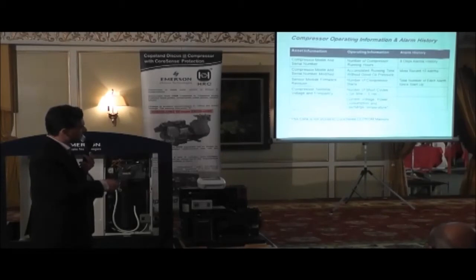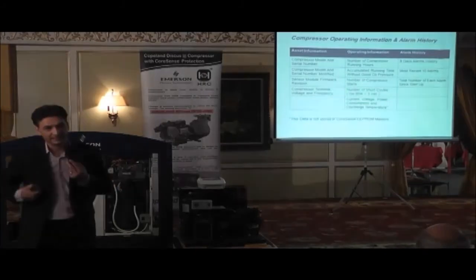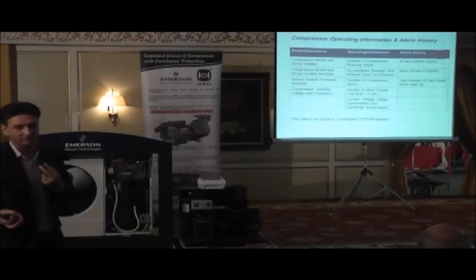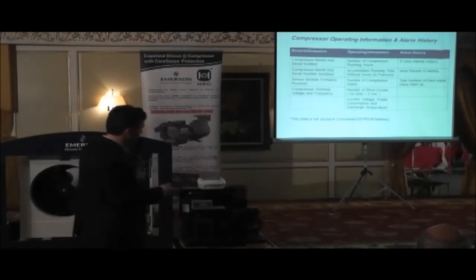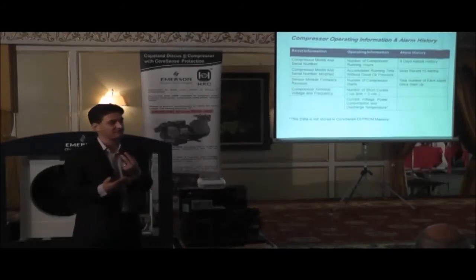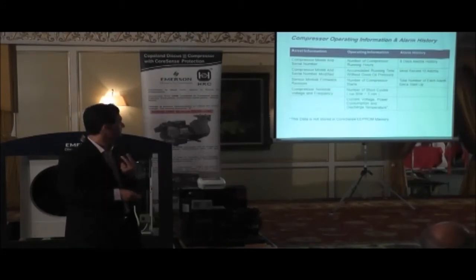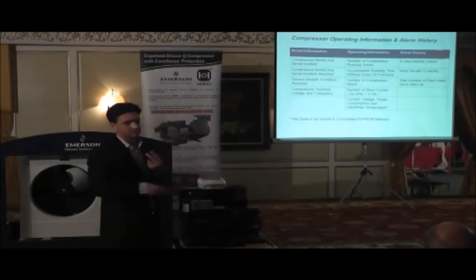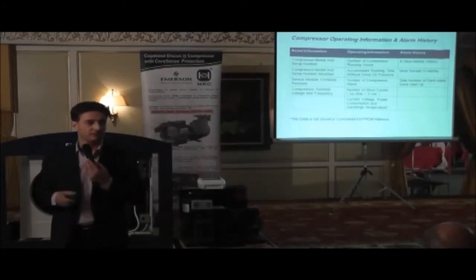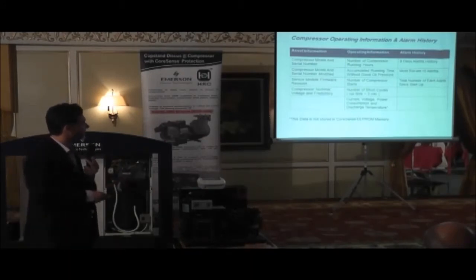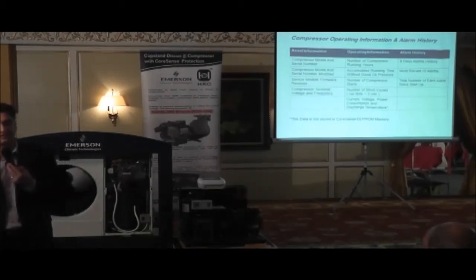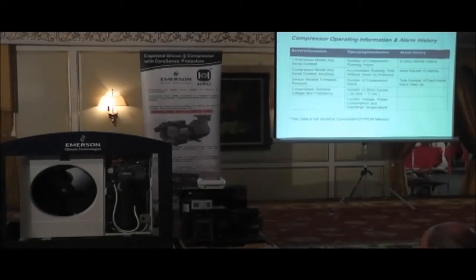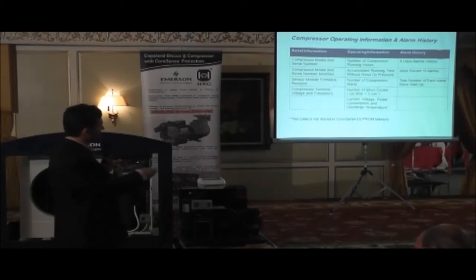Now when you connect your laptop to the compressor, this is what we call real-time data. You can connect your laptop, it will give you the current reading, the voltage, the power consumption, and the discharge temperature live on your laptop. Okay? So you know exactly how the compressors operate. And last but not least, there's a complete alarm history that is saved on that module. Okay? Now on the PC software, that alarm history will be displayed in 3 formats. And we've got the most recent, an 8-day, and then a yearly alarm count.